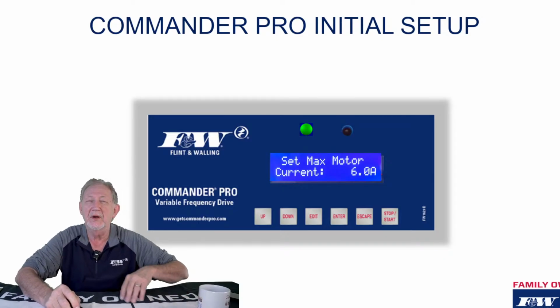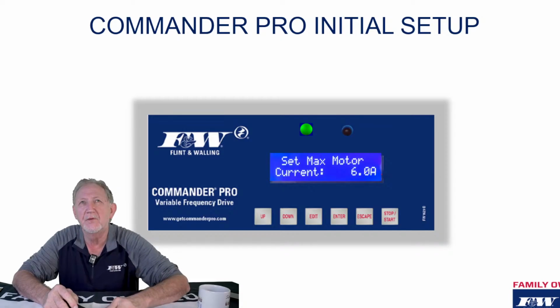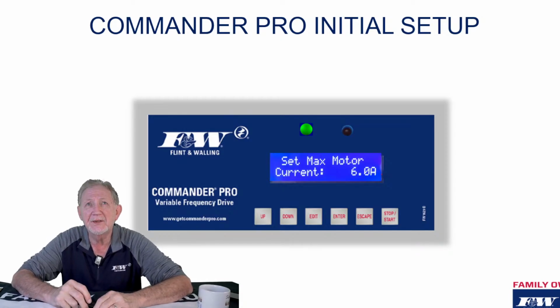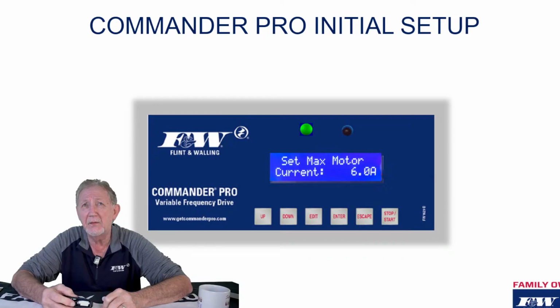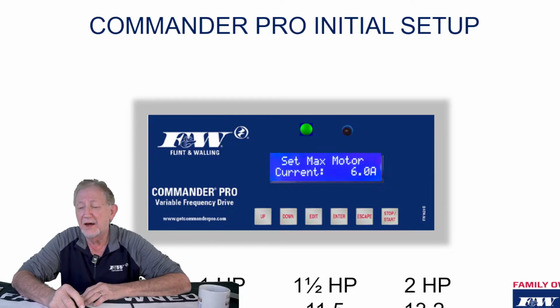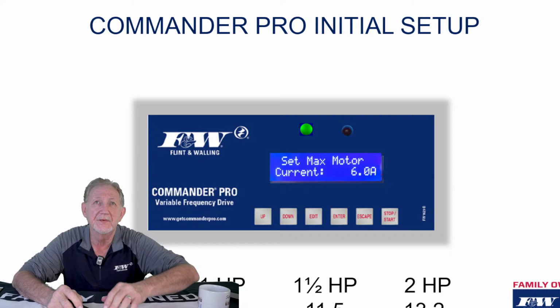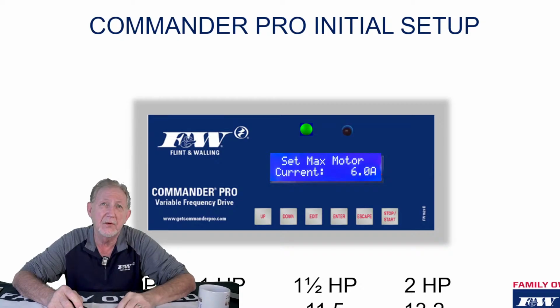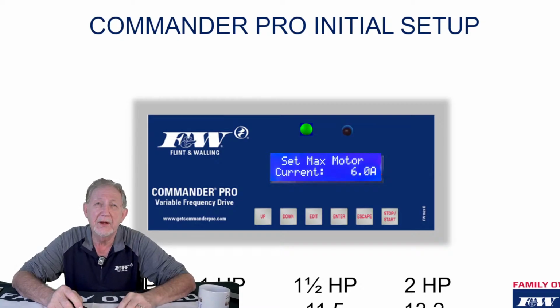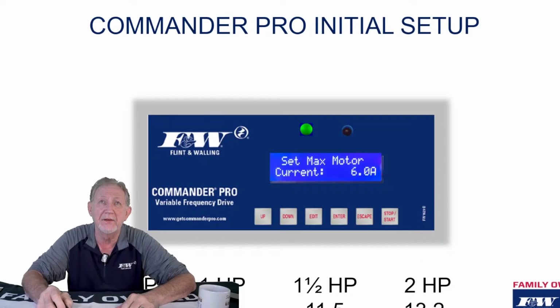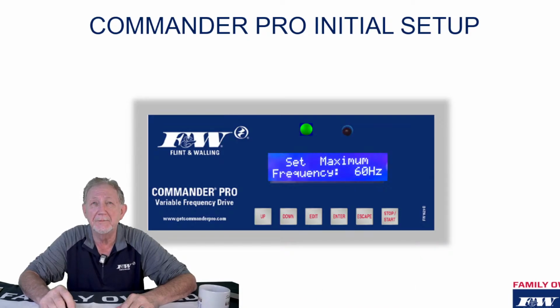And then this next menu, number 4, I think, on our menus here. This is where we're going to set that max motor amp. And again, when we look at that 6.0, that would be for a 1/2 horsepower submersible motor. You know, again, this is a 1.5 drive, so I can run anything up to that 1.5. So if I were running a 3/4 or a horse or even a 1.5, there's where I would change and put in the max motor amps for that specific horsepower. So that's where you would make this change. And that's what we're doing, is we're telling the drive what horsepower it's going to operate.